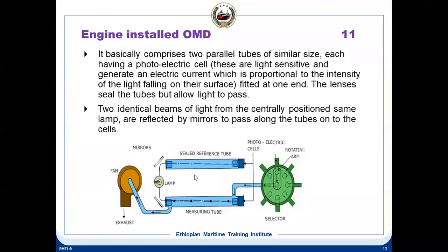You have to physically come and check it, because even if an atmospheric oil mist detector gives an alarm, it sometimes gives a false alarm. Yes, it can give a false alarm, because a lot of other conditions are there. Moisture can also give a false alarm, especially in steering gear rooms. Sometimes moisture can become very high and it gives a false alarm.